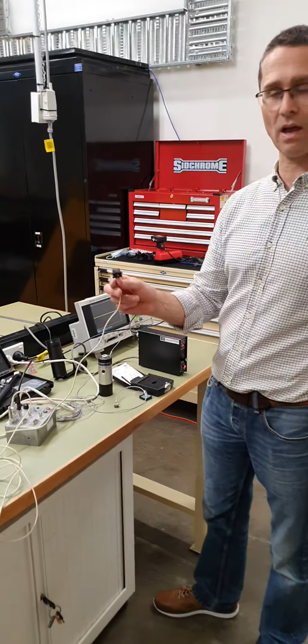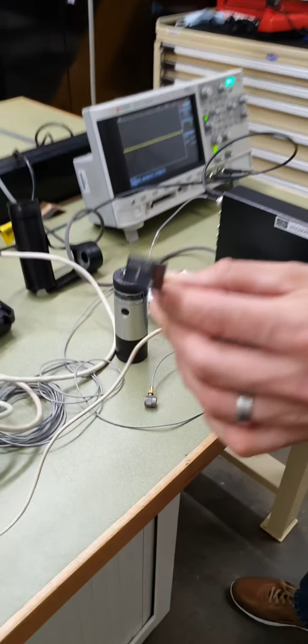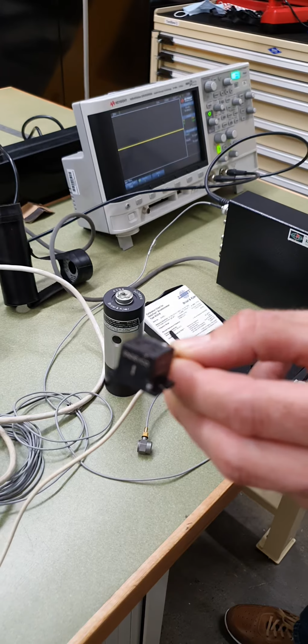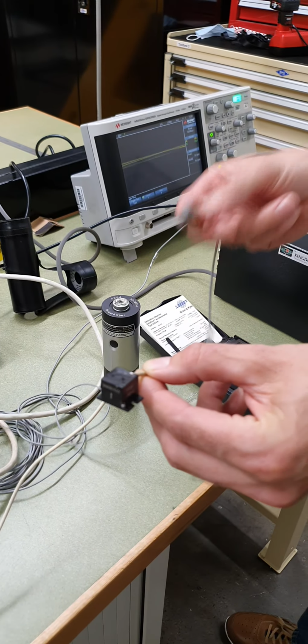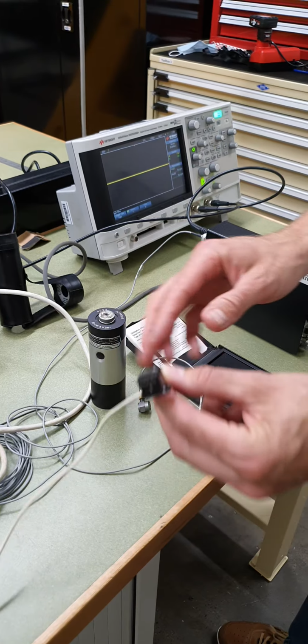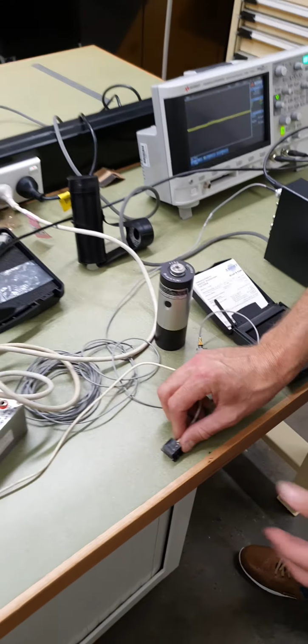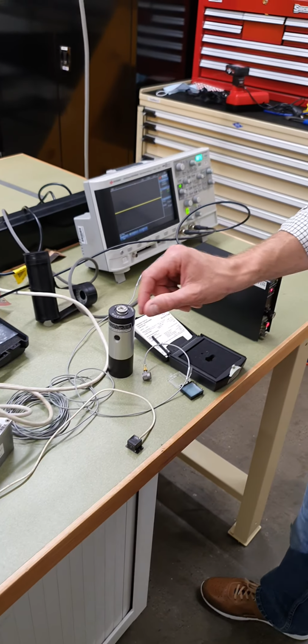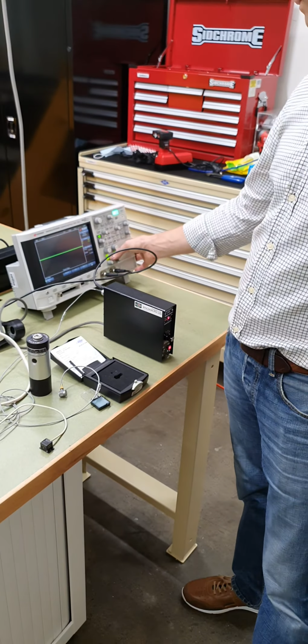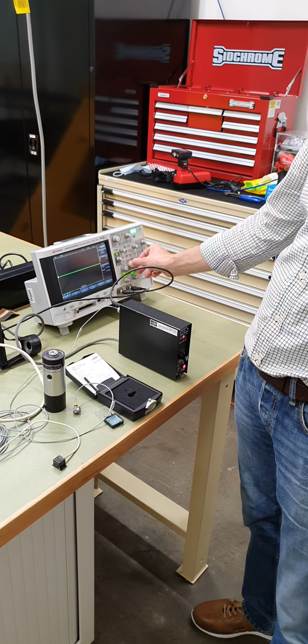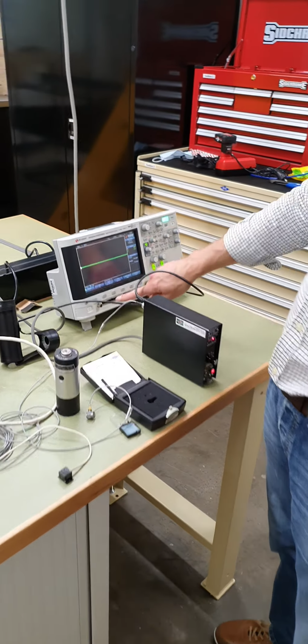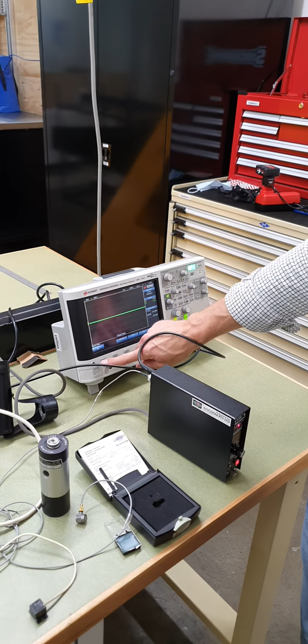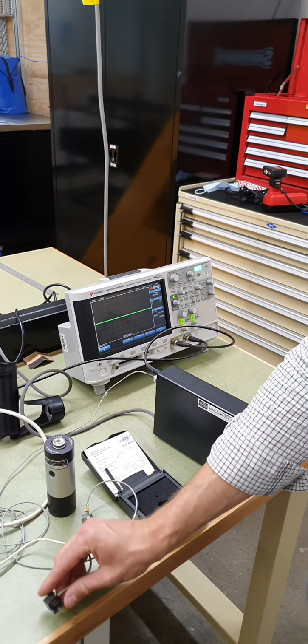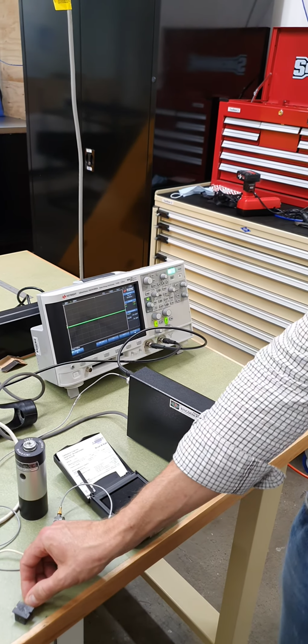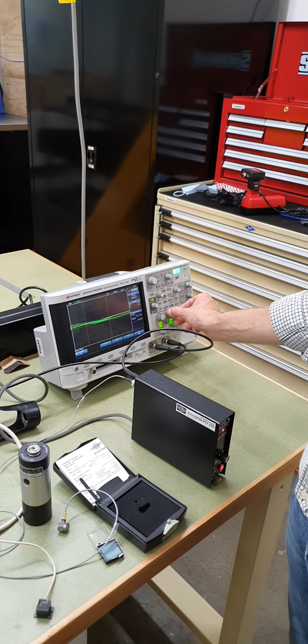Another type of transducer that we have here in the laboratory is this MEMS-based accelerometer. Rather than just measuring alternating vibration signal levels, this measures also DC. So this will measure acceleration due to gravity. If I put it on a flat surface, you'll be able to see that it will measure 1 G of acceleration. If I invert it, and I need to be DC coupled for this, which I am, then you should be able to see, as I turn it upside down, a different measurement coming through, but we're not yet properly set up. I'm not powered, actually. Sorry.